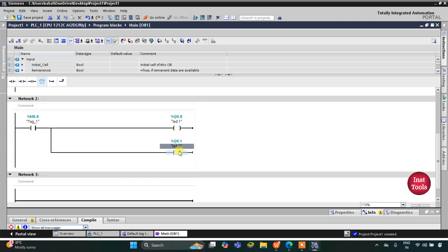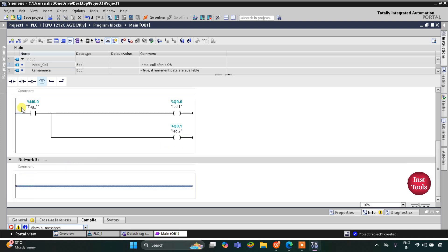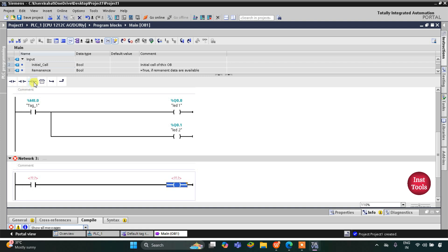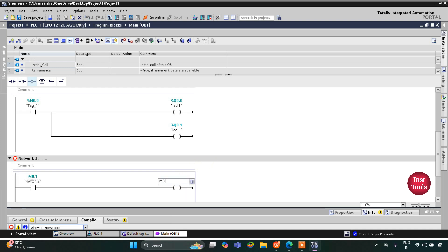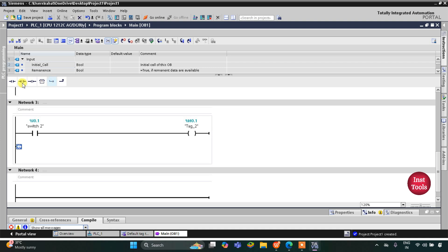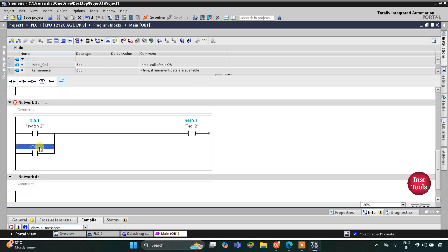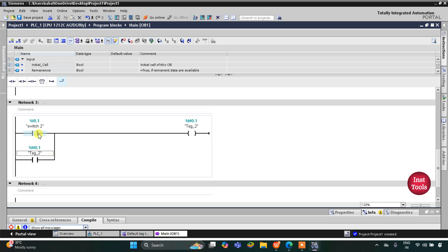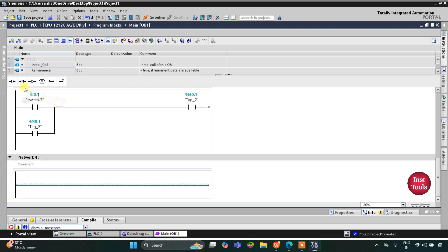Similarly for Switch 2, I will insert a normally open contact and assign its address as I0.1 (Switch 2). Then I will use a coil with memory bit M0.1, and latch it by opening a branch, inserting a normally open contact assigned as M0.1, and closing the branch. So when Switch 2 is turned on, M0.1 gets true, and when it is turned off, it still remains true. We use M0.1 here as a normally open contact.